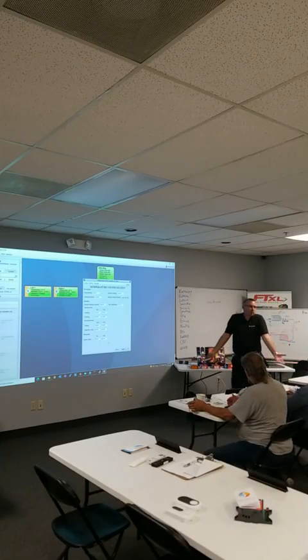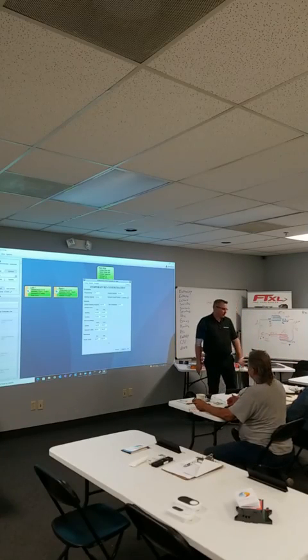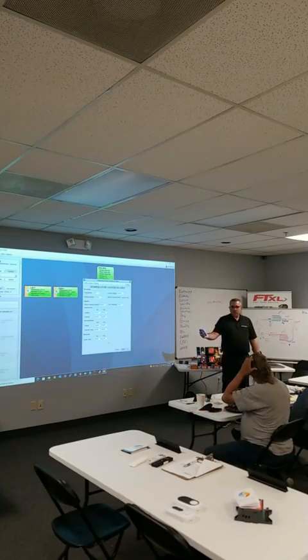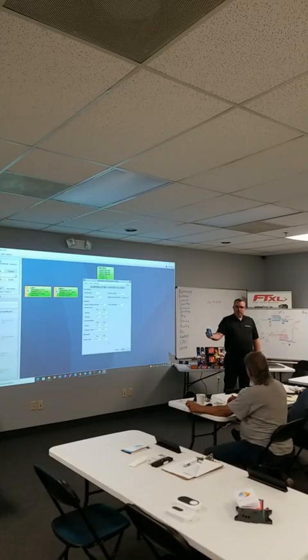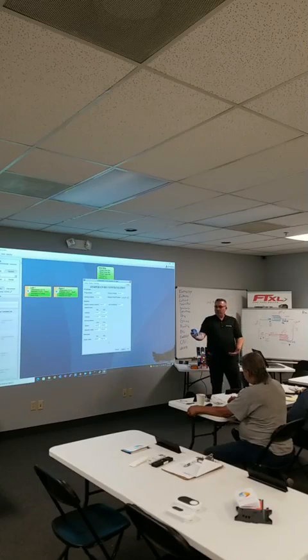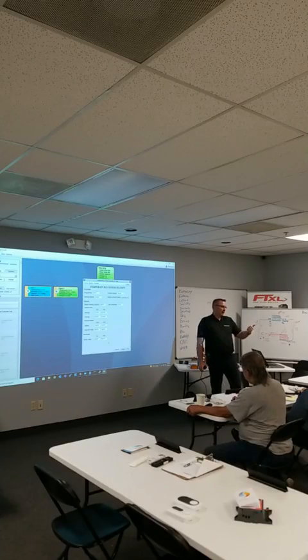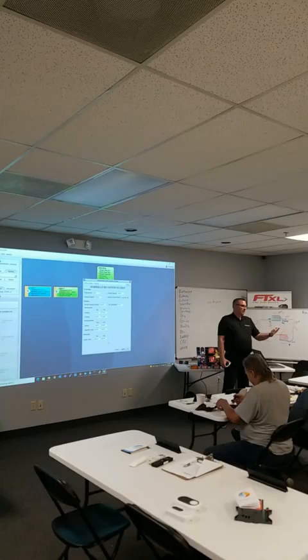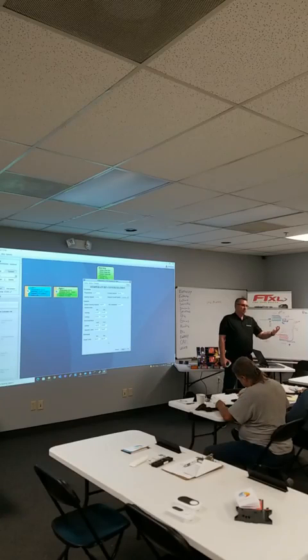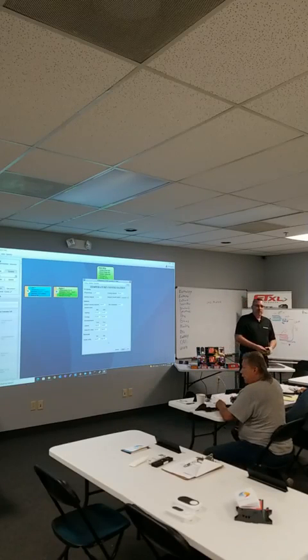If I get a call saying it's hot in here, I take this and see, yeah, it's a little warm but it's close to the set point. If I can see the inputs and outputs, the fan status and discharge air, and I'm calling for the compressor to run and see the fan's running, it'll tell you fan start-stop is on, fan status is true, the compressor's running, and you see you've got 50-degree air. What do I need to do now? But if you go to it, see where the tape is on the diffusers.